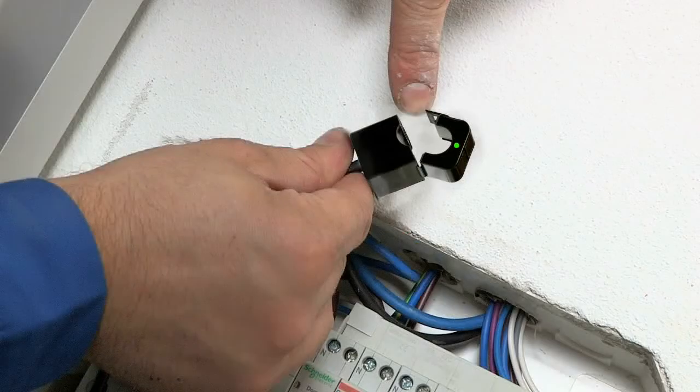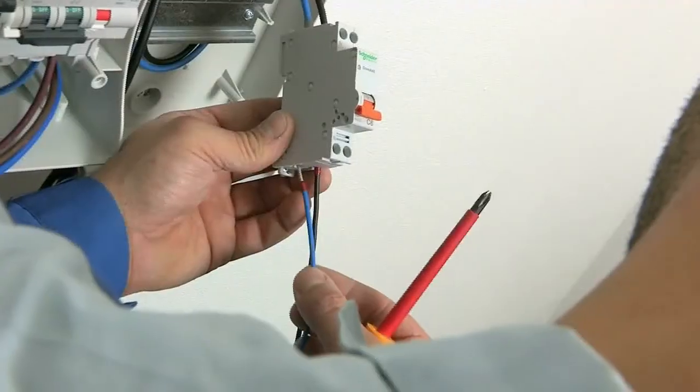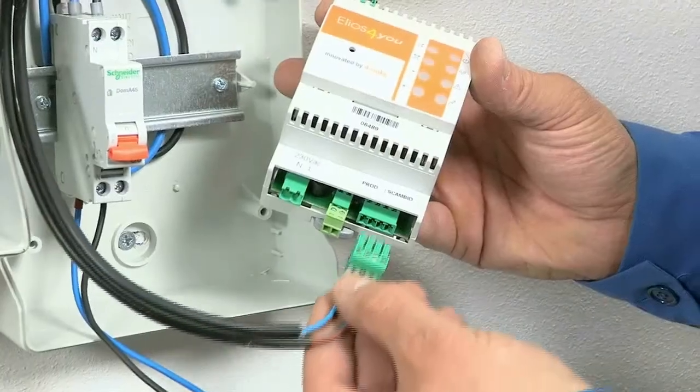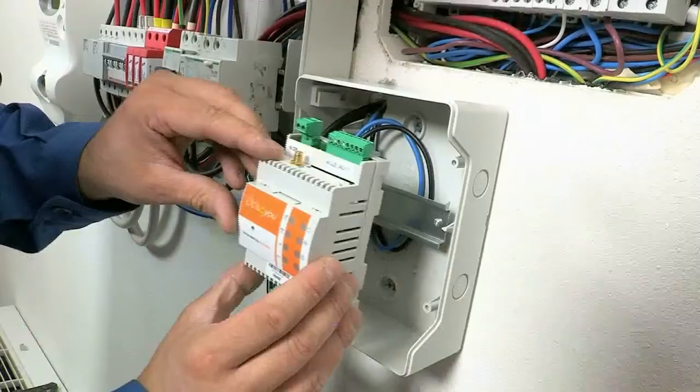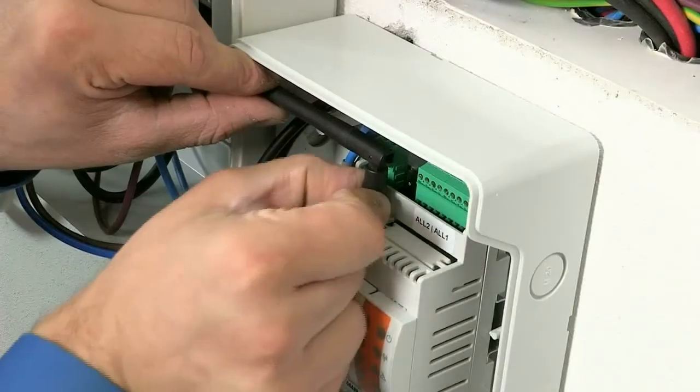Clamp the CT labeled generation over the live phase cable running from the generation meter, paying close attention to the orientation. Repeat the procedure with the mains CT. Complete the wiring to supply mains power to Elios4you and ensure the CT's terminal is secured. Mount the device and screw the antenna.